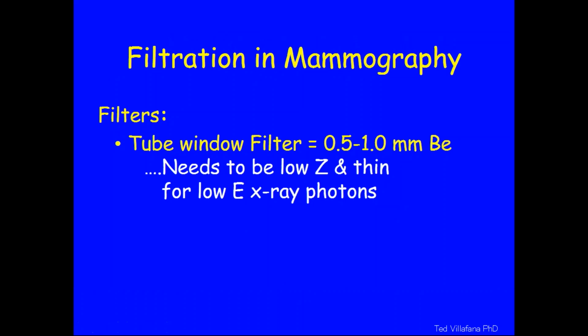Okay. How about mammography? We just saw a little while ago that a filter would wipe out a low energy beam. Well, in mammography, that's all we have is a low energy beam. So you don't have that 2.5 millimeters minimum. That does not apply to mammography. The 2.5 millimeters would completely wipe out the mammography machine output. So these mammography tubes are very specially built.